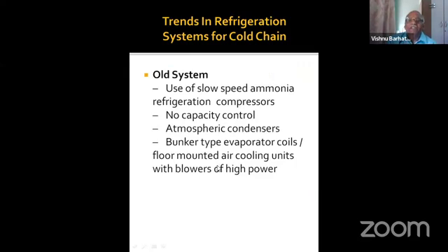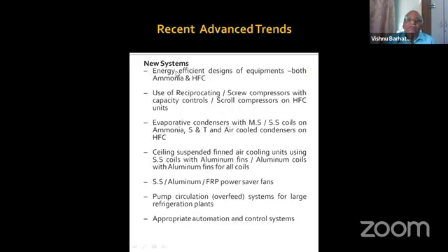Now for the refrigeration system also, because all other areas as well as refrigeration now, that also has been developed very efficiently. Earlier they used to have slow speed compressors. You must have heard about Frick compressor and Sabroe compressor, because they were very power consuming compressors. So this has gone. Then there was no capacity control, and the atmospheric condenser, where the water was falling and was collected at the bottom and then recirculated. This is also inefficient, and the bunker type of coil you have seen. These are all inefficient things. Now in the new system, very energy efficient designs, ammonia as well as other refrigerants are used. Then reciprocating as well as screw compressors are used, having capacity control. Then scroll compressors are also used.